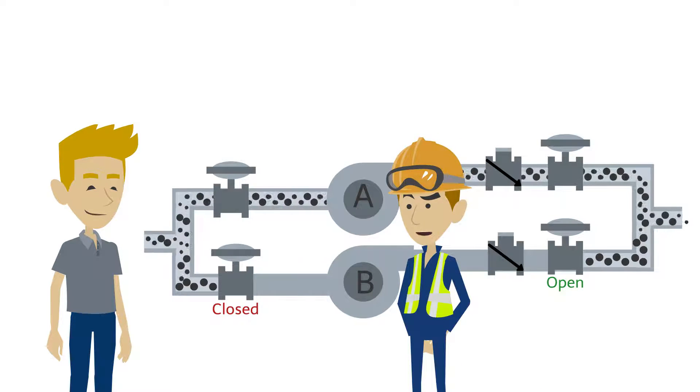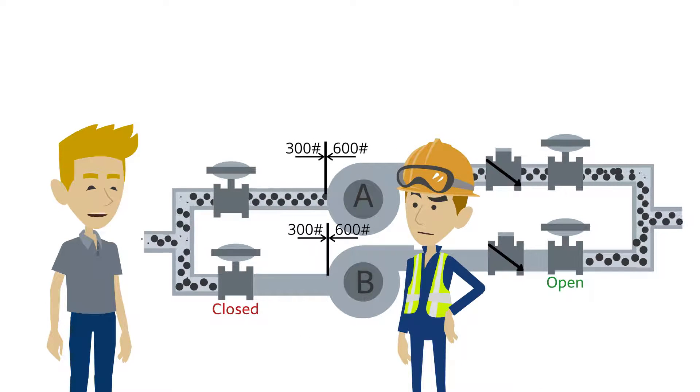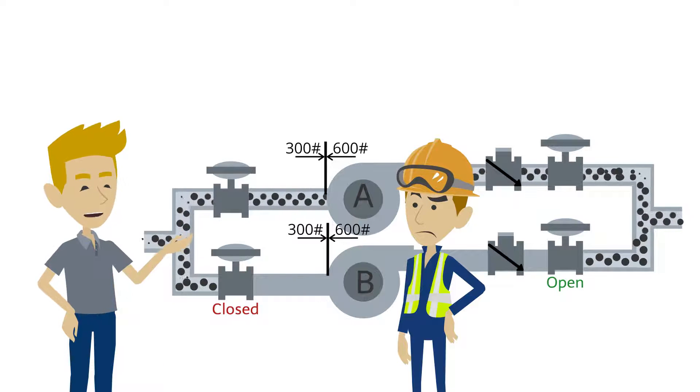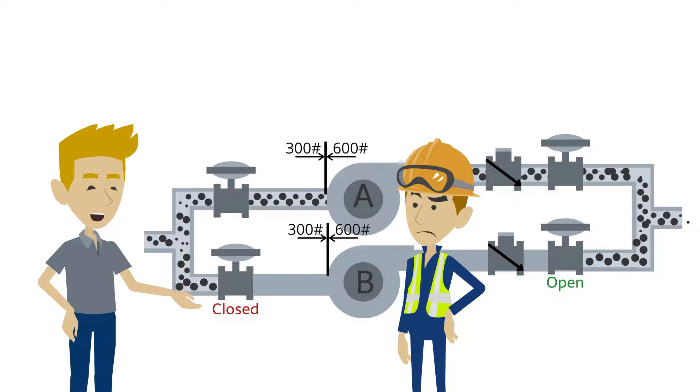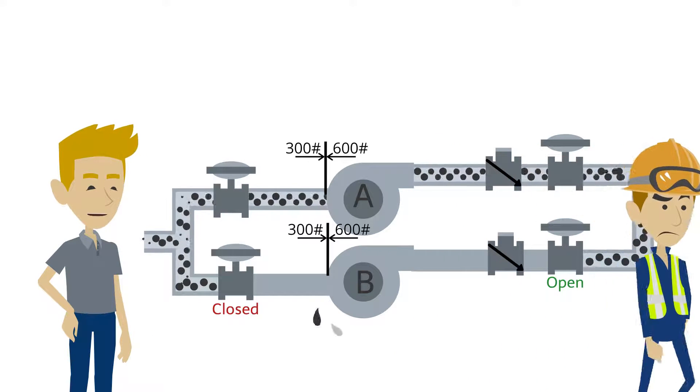Why was it leaking from the suction side? There is a spec break immediately upstream of the pump. High pressure fluid from the running pump A travelled back through the second tripped pump B to the suction side.